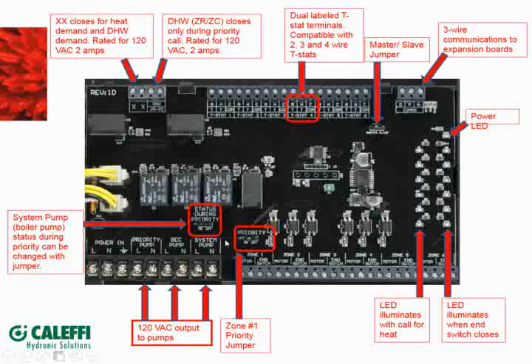And then we have the jumper for programming the status during priority. So basically what that means is if zone 1 calls for heat, or let's say an aquastat, your priority pump would fire. Keep in mind you're going to need a jumper. That's the one time we need a jumper here.